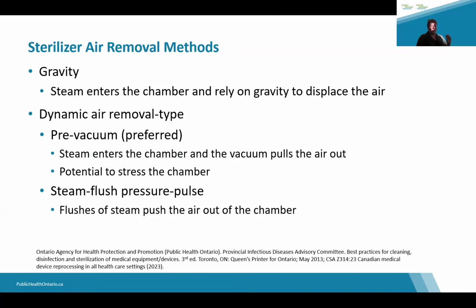And you should also be doing a weekly leak test to determine if there are any problems with the sterilizer's plumbing or seal. Okay, the pre-vacuum is the preferred autoclave type because it's more efficient in air removal than the gravity and is also better for lumen devices, and handpieces are lumen devices. Then we have the steam flush pressure pulse.